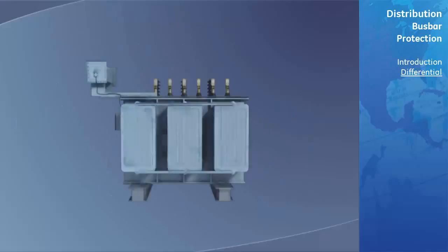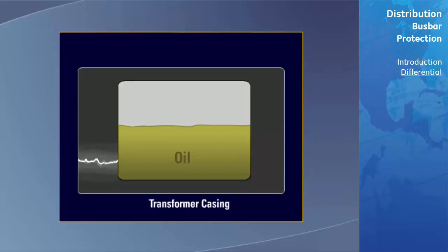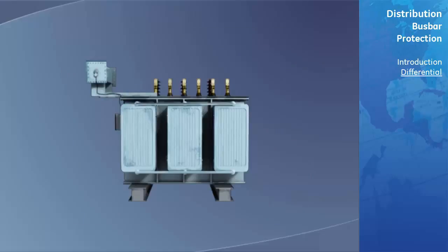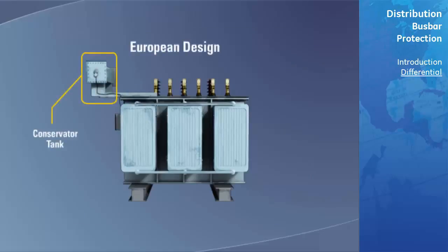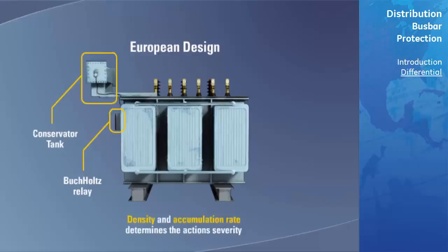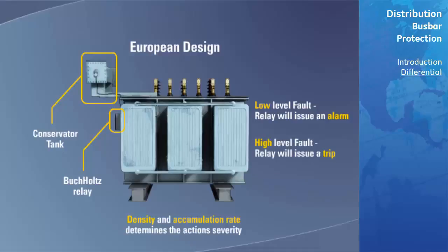Arc detection. When a high or low-level fault occurs within the transformer, usually an arc forms. This arc causes the oil within the transformer to break down and gas is formed. The speed at which the gas is formed is proportional to the size of the arc and hence the fault. The transformer design determines how this gas is detected. In European transformer design, there is no space for the gas to collect, so a conservator tank is connected to the transformer. A gas accumulator device, known as a Buchholz relay, is connected between the transformer and the conservator tank or tanks. If a low-level fault results in arcing, the small amount of gas that is produced will accumulate in this relay, which will then issue an alarm. If there is a sudden large increase in the amount of gas being produced corresponding to a large fault, the relay will sense this and trip the transformer offline.